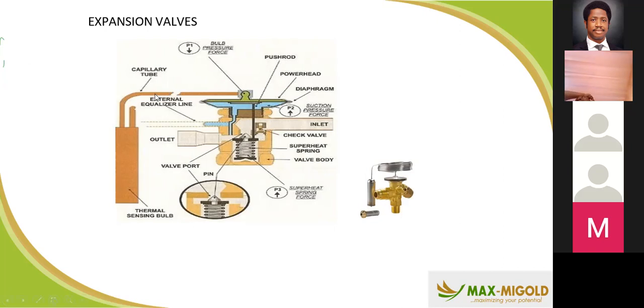So don't forget, because all these pipes are small, they could be blocked. And that blockage could slow the flow of refrigerant gas in and out of this particular component. And where does the blockage come from? It is when they are installing. When you bring in a technician that does not understand the principle of installation, the standard is that nitrogen gas must be passed through the copper pipe while you are brazing.